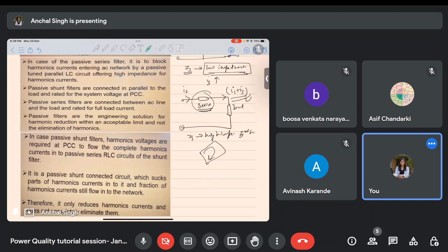So in case of passive shunt filters, harmonic voltages are required at the point of common coupling to flow the complete harmonic current to the passive series RLC circuit of the shunt filter. So when we talk about the location, the passive filters are located very close to the loads. We have to take care of this so that they compensate for the problem there itself, and the source does not have to give any kind of bad current.